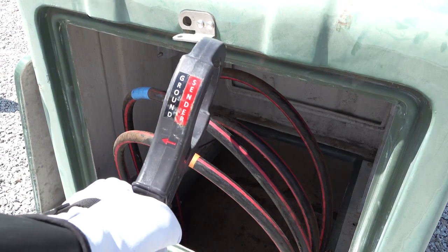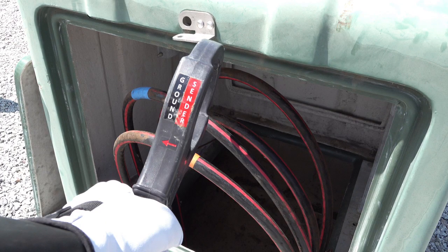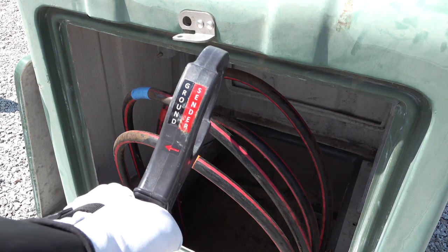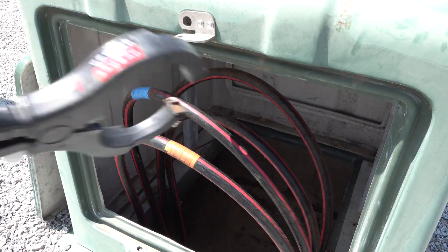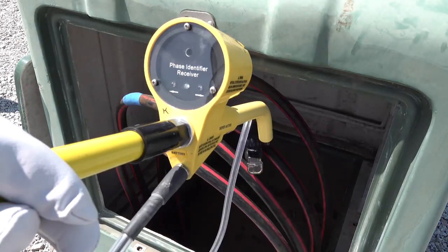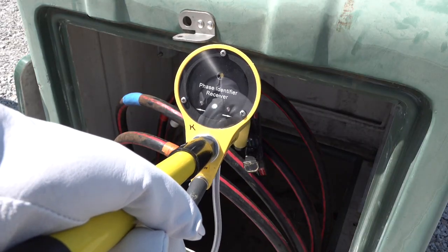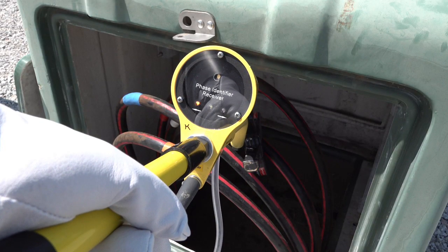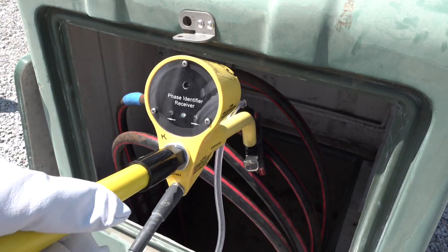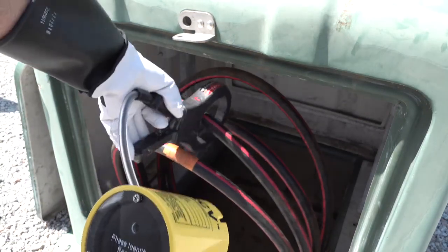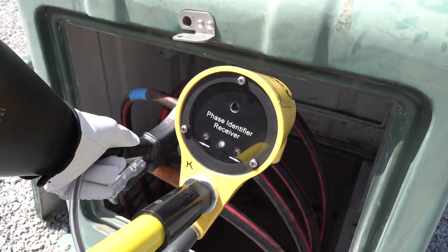When using the CT clamp, take note of the red arrow located on the side of the unit. The red arrow must be pointing away from the ST800 or the sender and towards the ground or your concentric on the far end. Insert the CT clamp plug into the receptacle located at the bottom of the STRCV and clamp it around the primary cable to be identified. Notice your directional arrow pulse on the STRCV. Again, since we have the red lead attached to the concentric on the near end, the pulse arrow is pointing away from the ST800 towards the concentric on the far end. Clamp the CT around the remaining primary cables and verify that there is no pulse on them.